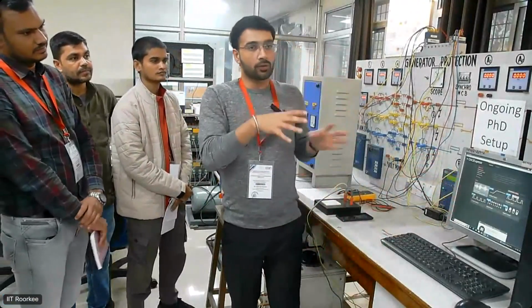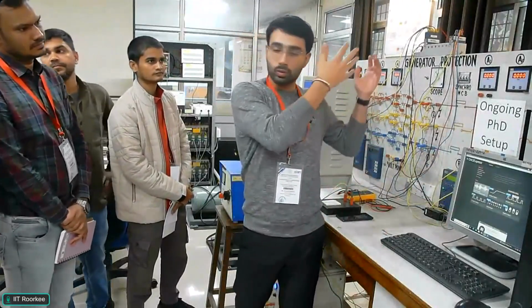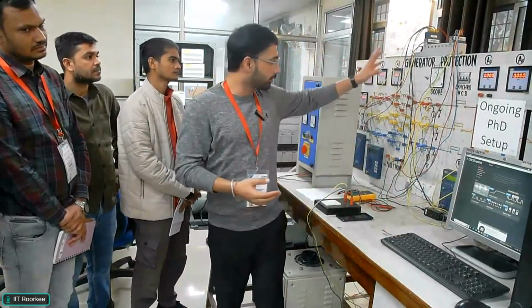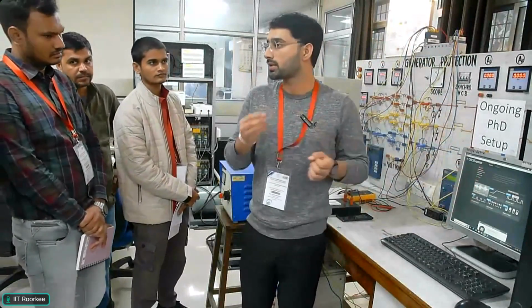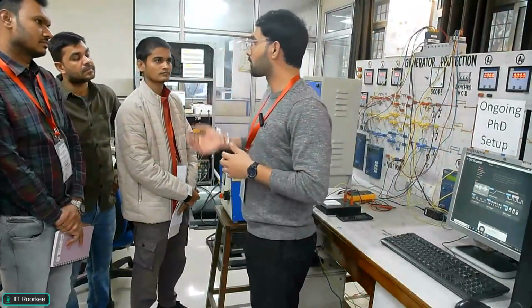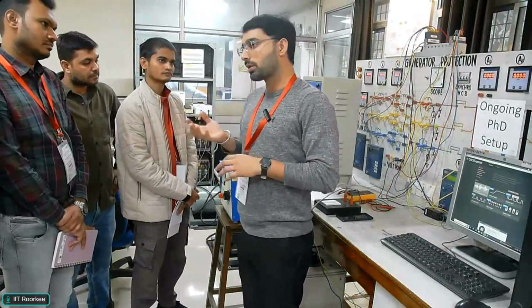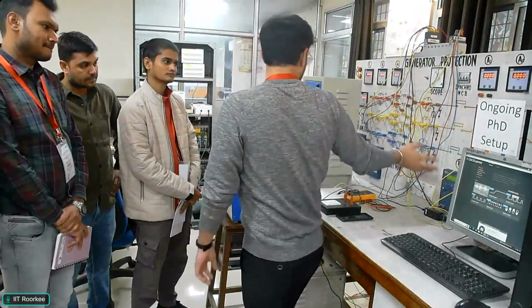So whatever fault analysis, whatever will happen in real time, I can take all that data through this NI DAQ, and I've connected it for my voltage and current measurements. All that data I can gather in this and take into my Excel sheet. Further, I can utilize that data for my algorithm purposes, for my real-time simulations, or any algorithm I want to design based on the analysis. Then I can again put it into my relay system.